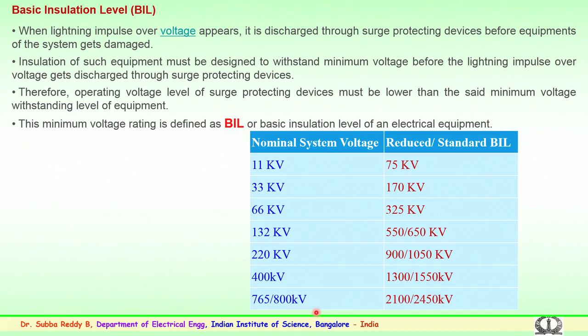So, I am again repeating this slide as this is very important information, where the factors which determine the insulation strength of any equipment are based on these values. Above 200 kV, above 220 kV systems, lightning and switching surges play a very dominant role. So, the BIL values of this equipment have to be seen so that they meet the requirements for various overvoltage surges.